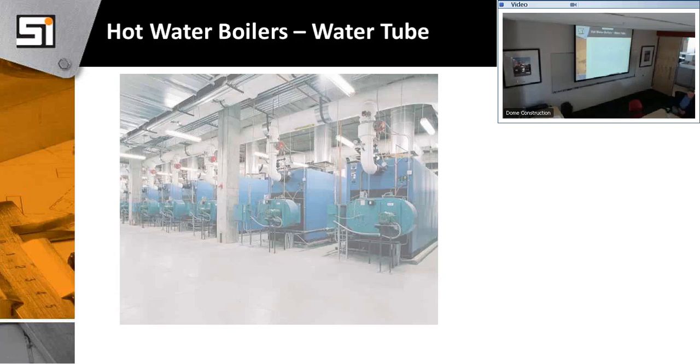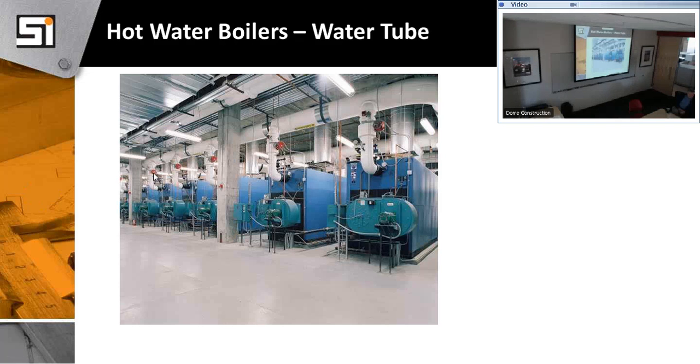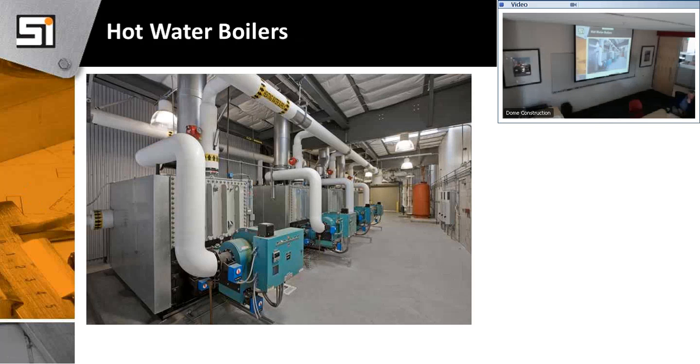Condenser water is the water taking the heat away from the chiller. The chiller is making the chilled water, which is what's going out to your heat exchange. Condenser water goes to the cooling tower, where it's rejecting heat. Those are boilers. That's how we make hot water.